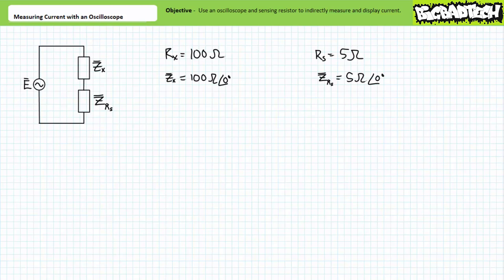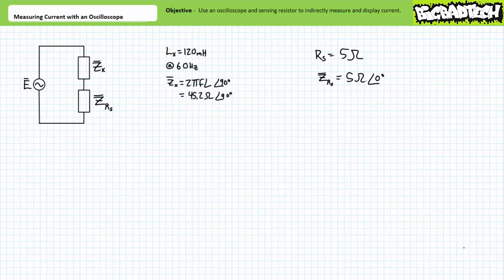Sizing a sensing resistor for reactive elements necessitates a bit more thought, since the impedance magnitude for reactive elements like capacitors and inductors is a function of frequency. Consider a 120 millihenry inductor subjected to 60 hertz AC. The inductive impedance formula makes it clear that this inductor presents an impedance of approximately 45.2 ohms at an angle of positive 90 degrees. A 5 ohm sensing resistor might be a little too high for this application, since 5 ohms is only one-ninth of the inductive impedance magnitude at this frequency. Perhaps a 2 or even a 1 ohm sensing resistor might yield better results.